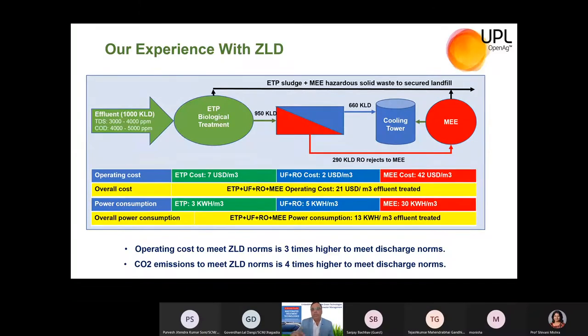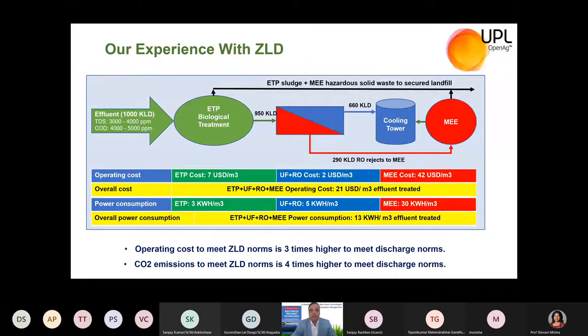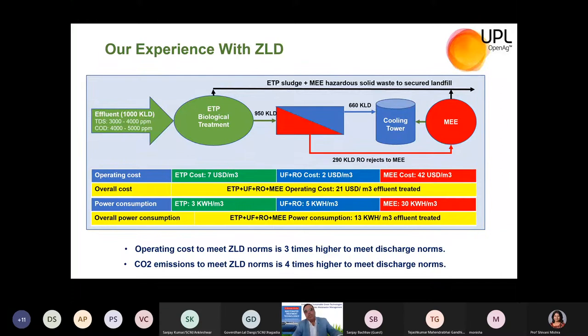Energy consumption is two to four times higher when you embed ZLD with a standard wastewater treatment plant. Taking a practical example of one MLD wastewater that gets treated to achieve ZLD: first, ETP biological treatment is applied, then a reverse osmosis system, and from the RO reject, treatment is done through MEE. The permeate RO water is utilized in a cooling tower, achieving zero liquid discharge. The operating cost just to operate conventional biological treatment is nearly seven USD per cubic meter.